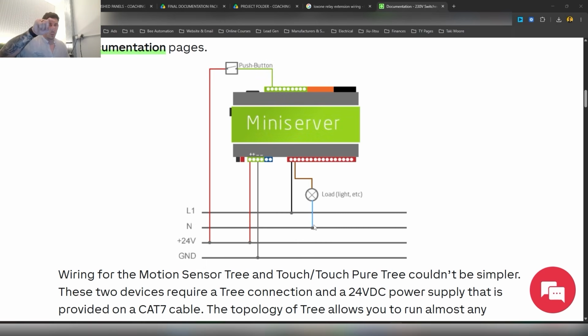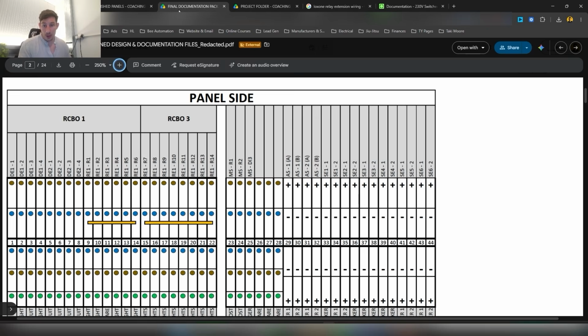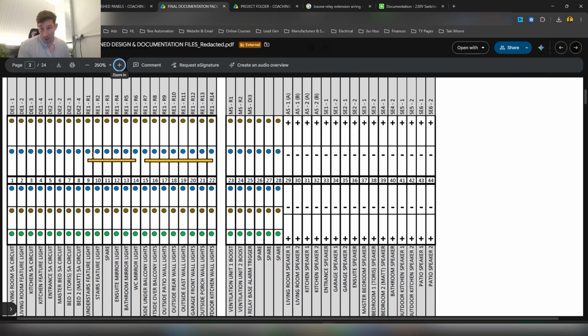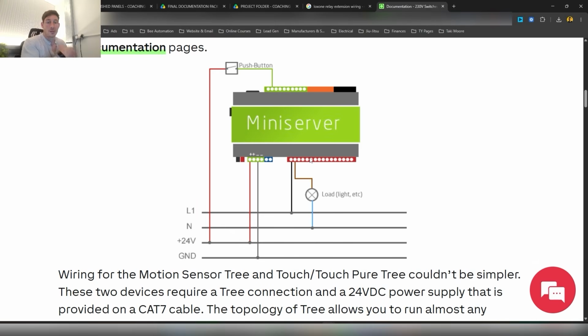And this neutral supply, again, we're going to be going through a terminal block in the panel, but that neutral supply is just, you'll see later on, taken straight from the RCBO down to the terminal block, and then distributed with a little bus bar across all of those terminals - just one, B1 neutral, then bussed across here. But yeah, that's what we're doing wiring-wise for the relay extension at the moment.